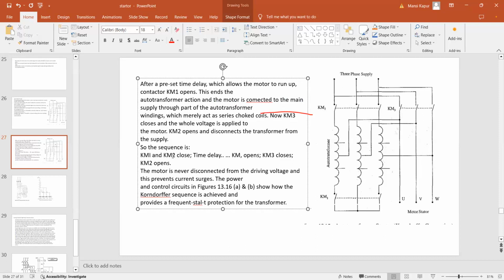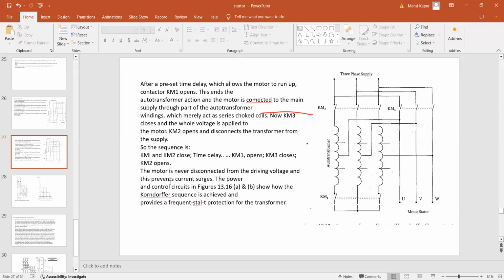So the sequence is KM1 and KM2 close. There is some time delay, then KM1 opens and KM3 closes, then KM2 opens. So that your auto transformer is completely isolated from the system. The motor is never disconnected from the driving voltage and this prevents current surge. So at any point of time, the motor is not disconnected from the voltage. When KM1 opens, KM2 is still supplying the voltage to the motor, right?